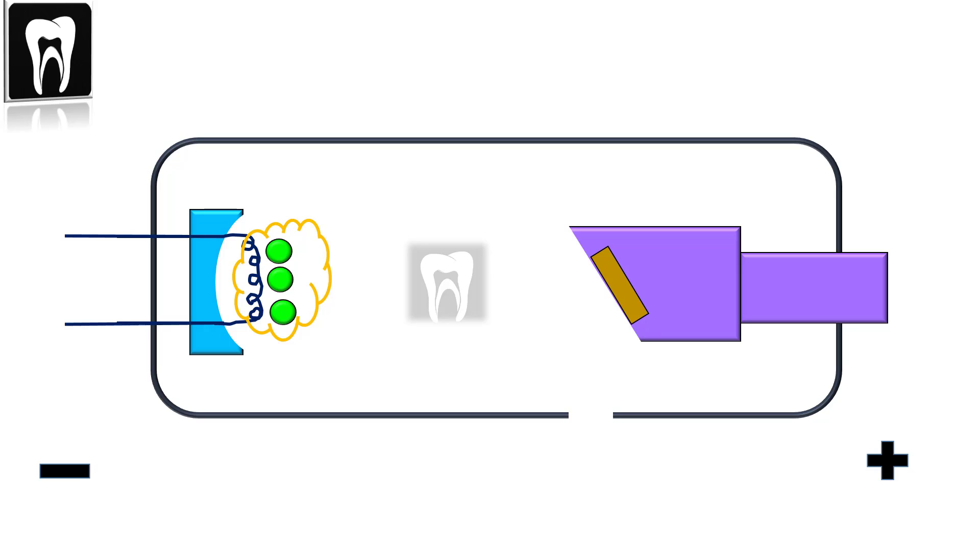The negative focusing cup pushes the negative electrons toward the anode and focuses them into a small area called the focal spot.